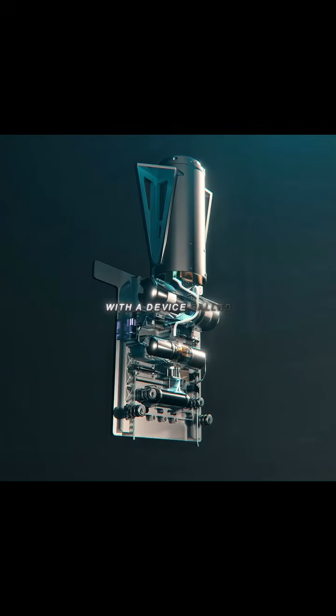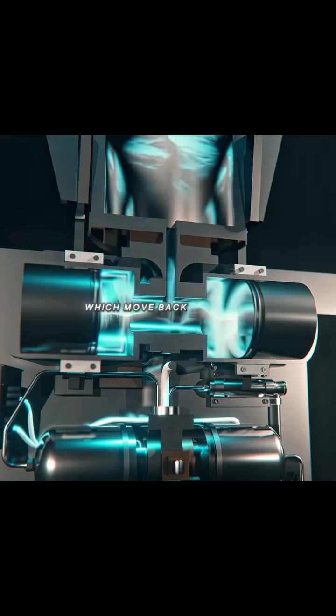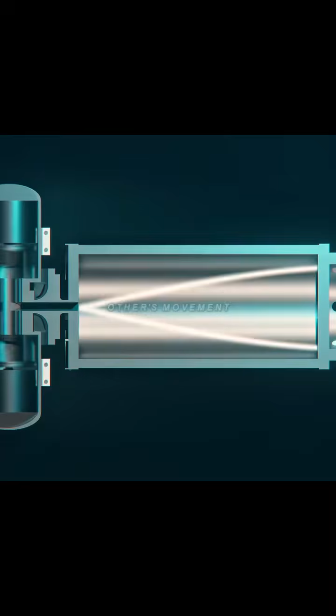The cooling process all starts here at the bottom of the telescope with a device called a pulse tube. Inside these tubes are two pistons which move back and forth to compress the helium into the pulse tube. Since this movement would create a lot of unwanted vibration, these pistons have to move in the exact opposite direction with precision timing to cancel out each other's movement.